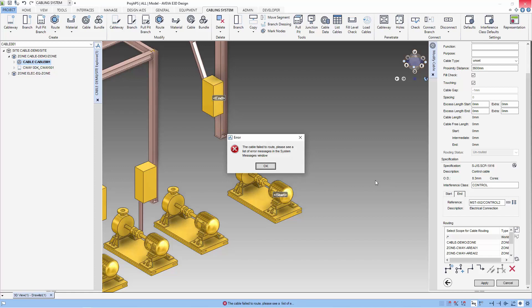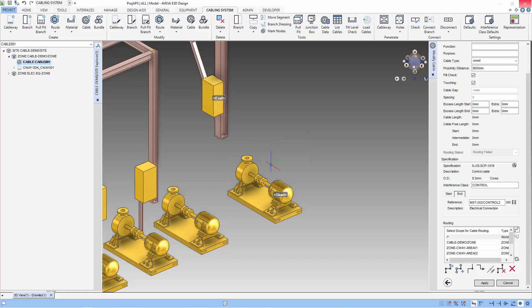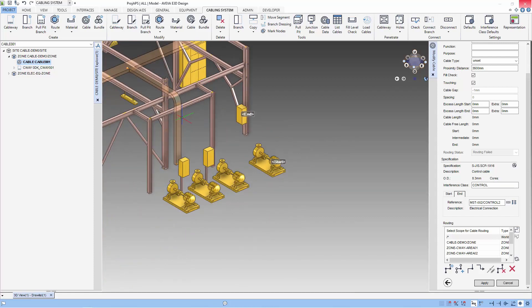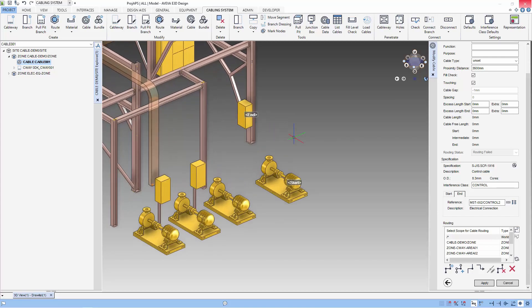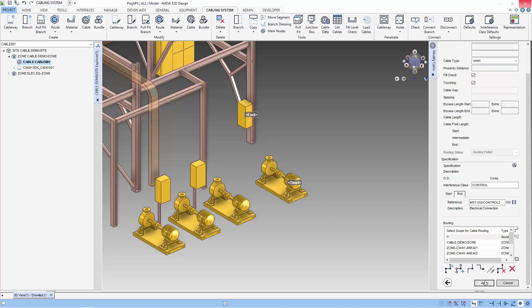We have an error message because the start and end point couldn't find points for the cable to route like cableway attachment point. So for this case, what we can do is to increase the proximity distance. Remember to apply after changing the proximity distance. Let's route again.